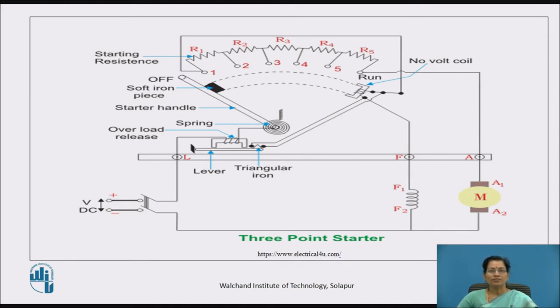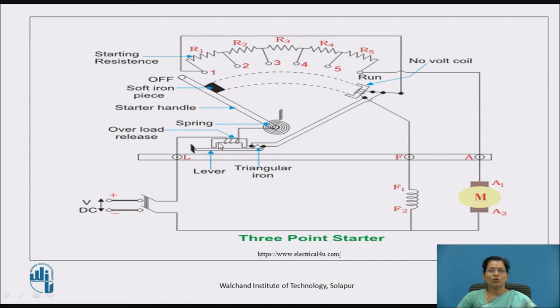This is the 3-point starter. The name '3-point' is given because there are 3 terminals: L, F, and A — where L is connected to the supply voltage, F is connected to the field winding of the motor, and A is connected to the armature winding. The different parts include the resistance connected in series with the armature winding, the arm or starter handle, spring, lever, and a triangular iron provided for the overload coil. This is the no-volt coil, and this is the off position.